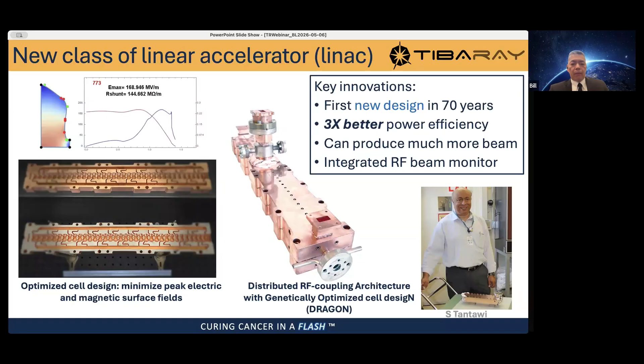So by optimizing the exquisite shape of the accelerating cavities within the linear accelerator and distributing the power in a novel way, this new design, prototyped at Stanford University and SLAC National Accelerator Lab, you can see Sami with a picture there, demonstrated these principles that showed much better power efficiency, which means that we can use the same amount of power to produce much more beam. And that's the technology that is now being realized within TibaRay.